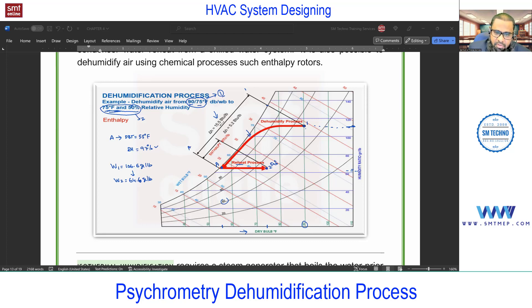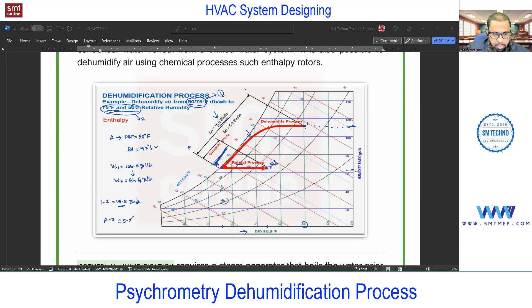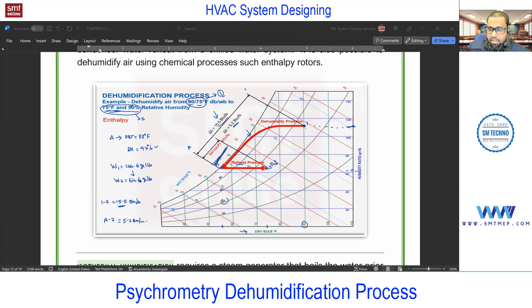Now the enthalpy: from point 1 to A, the delta-H for cooling is 15.5 BTU per pound. To get from condition 1 to A, this much heat extraction is required, including both sensible and latent components. From A to 2, the heat addition required is 5.2 BTU per pound — sensible only. You can verify these values on the psychrometric chart.